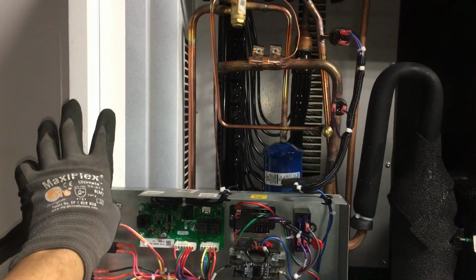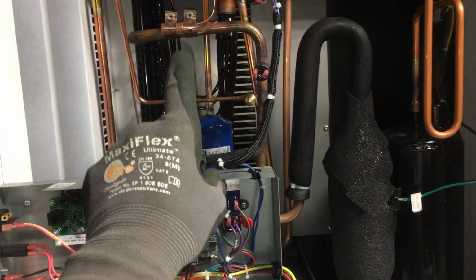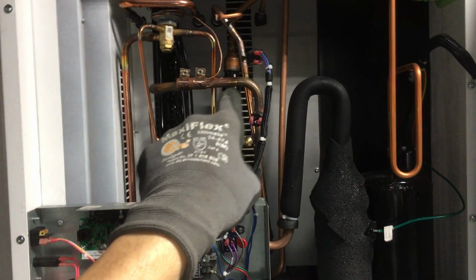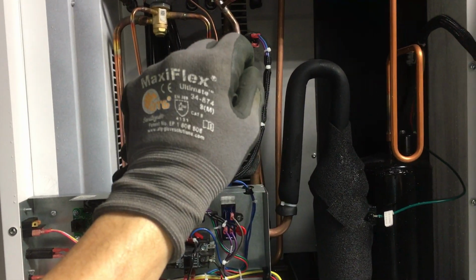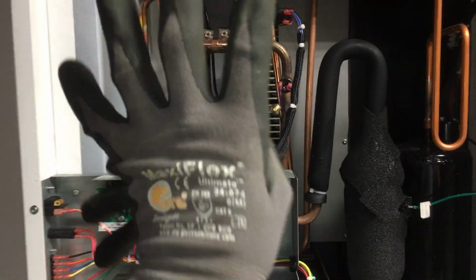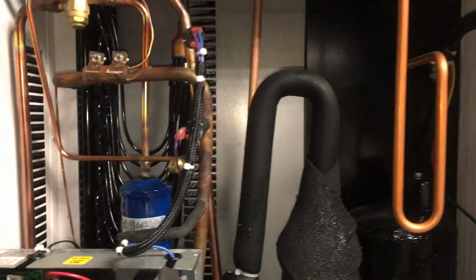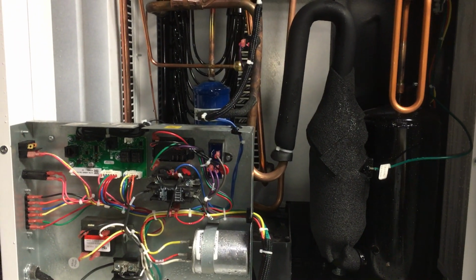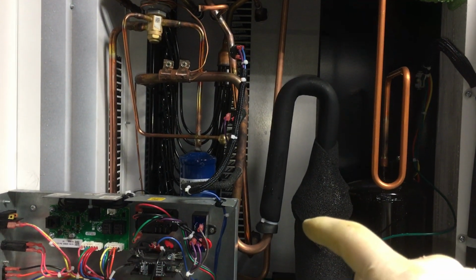We have a dehumidifier that was meant to be placed inside the location which it's dehumidifying. That is how this is designed, because it has so many air leaks on it. It doesn't matter if it leaks within the same room that it's dehumidifying, because humidity and temperature and everything is all the same. So what is going on here is it was placed outside of the room in which it is dehumidifying.